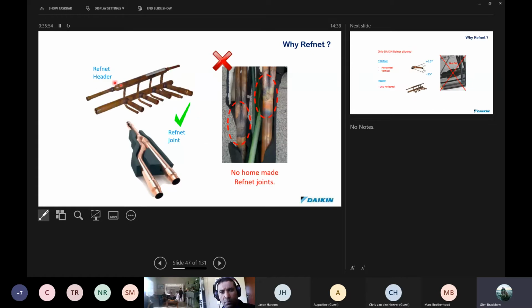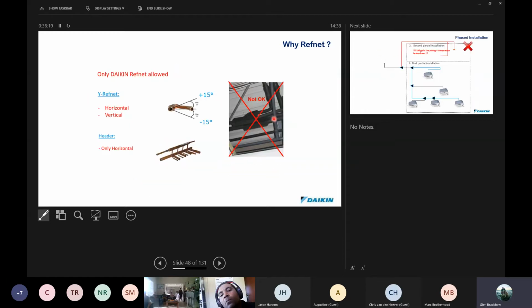We spoke earlier about Refnet headers, with a header joint. Remember, they must be horizontal, and this is what a typical Refnet joint looks like. It's a Y joint, and it comes with its own insulation. You're not allowed to do your own homemade ref nets like this. These are not acceptable. Where we have found these in systems, we've had plenty of compressor failures because they are not designed properly.